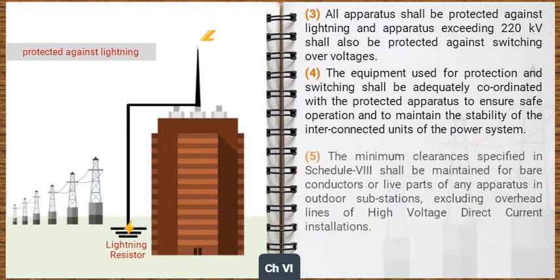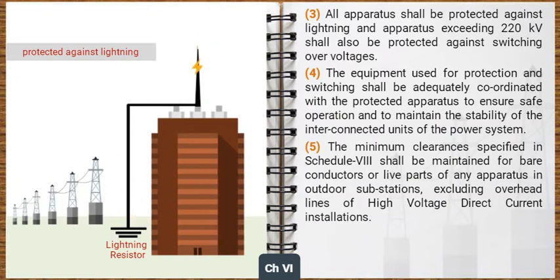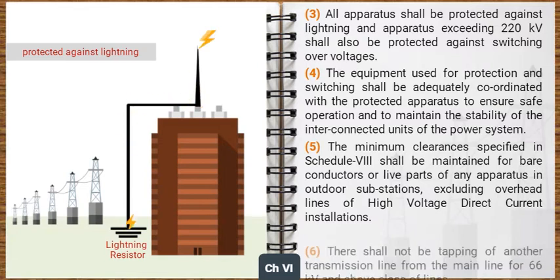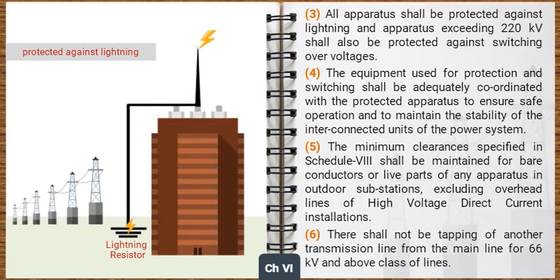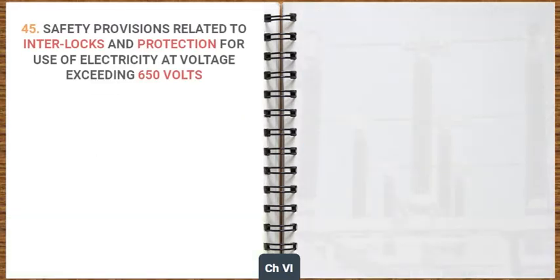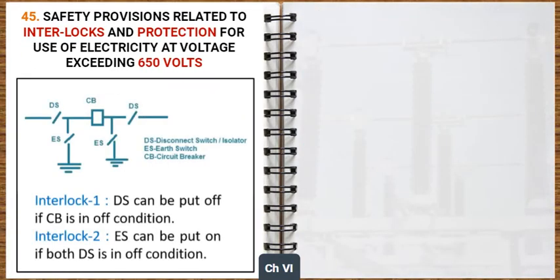The minimum clearances specified in Schedule 8 shall be maintained for bare conductors or live parts of any apparatus in outdoor substations, excluding overhead lines of high voltage direct current installations. There shall not be tapping of another transmission line from the main line for 66 kV and above class of lines.